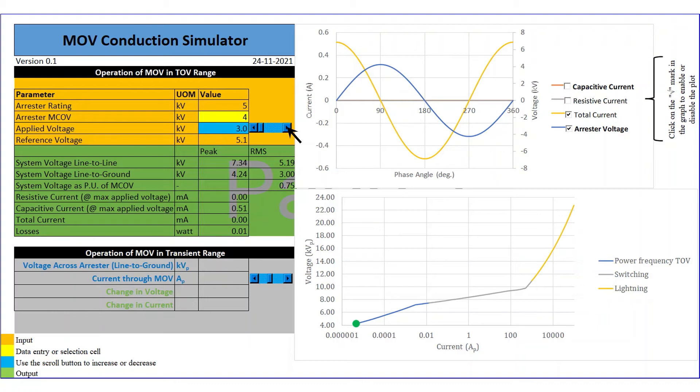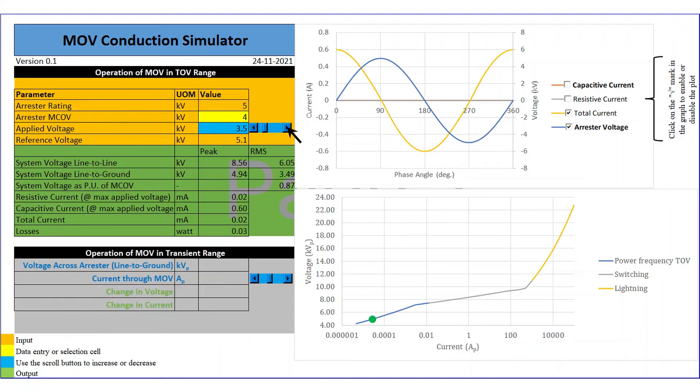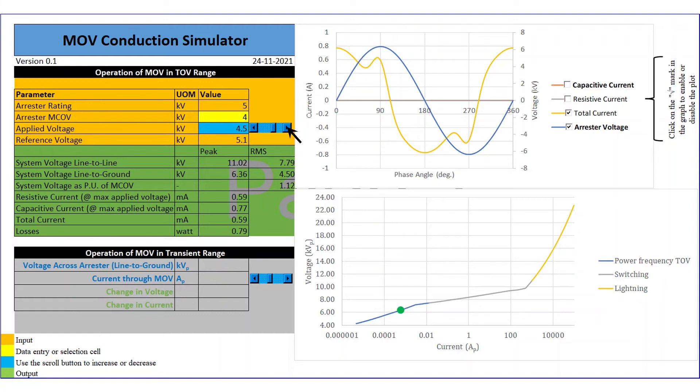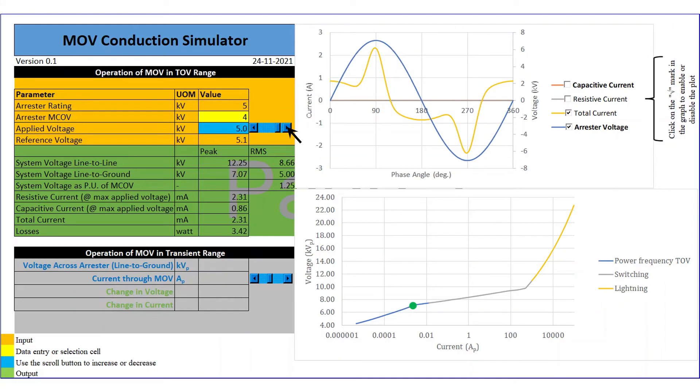Now you can see as we increase the applied voltage, how the current waveform is changing from pure capacitive, which is represented as a sinusoidal in shape and nearly 90 degrees out of phase from the voltage waveform into a different shape, which is a mix of capacitive and resistive current. Simultaneously, see how the cursor moves on the VI curve. It is also important to note that with a small change in the voltage, the current is rapidly changing. Watch this section of video once again for clarity.